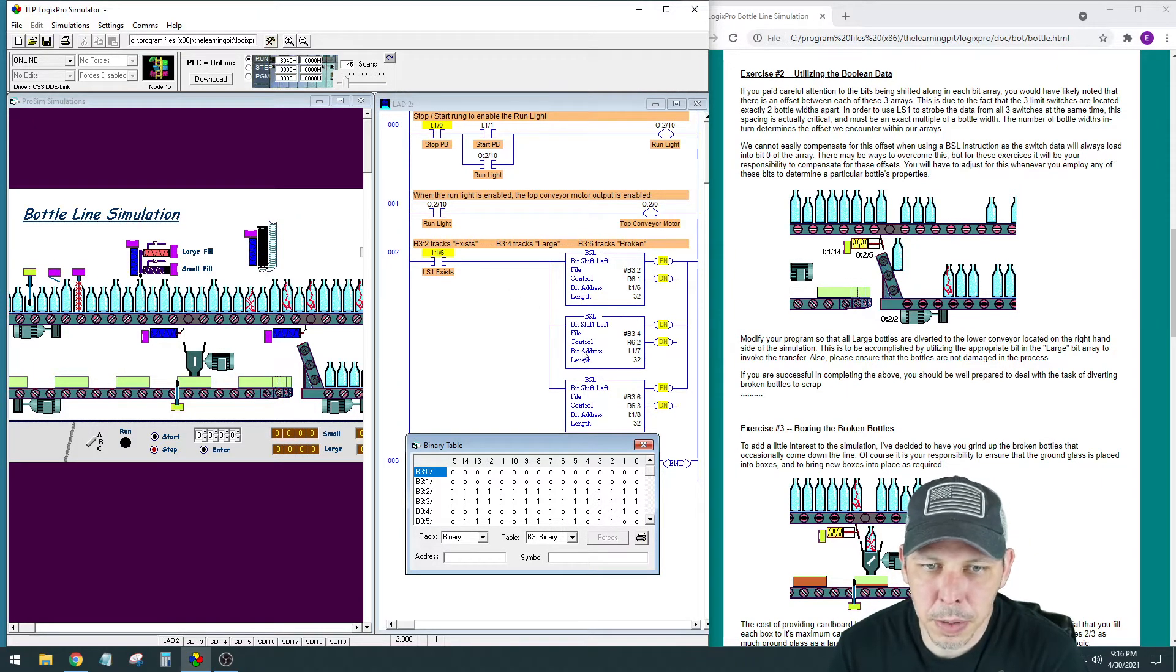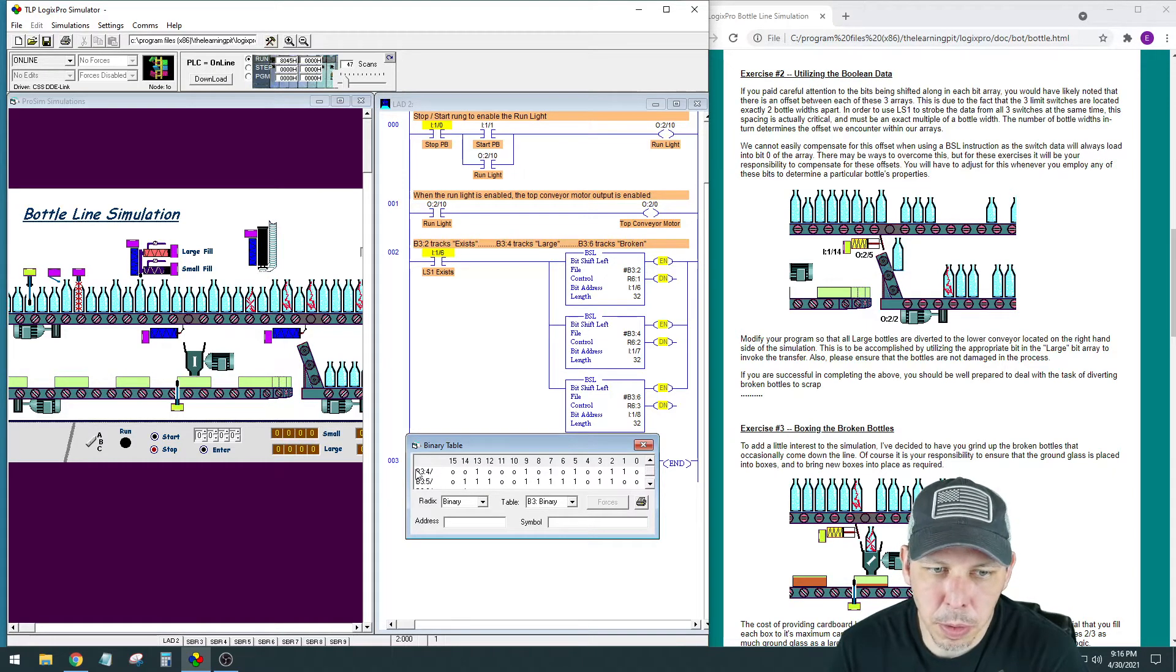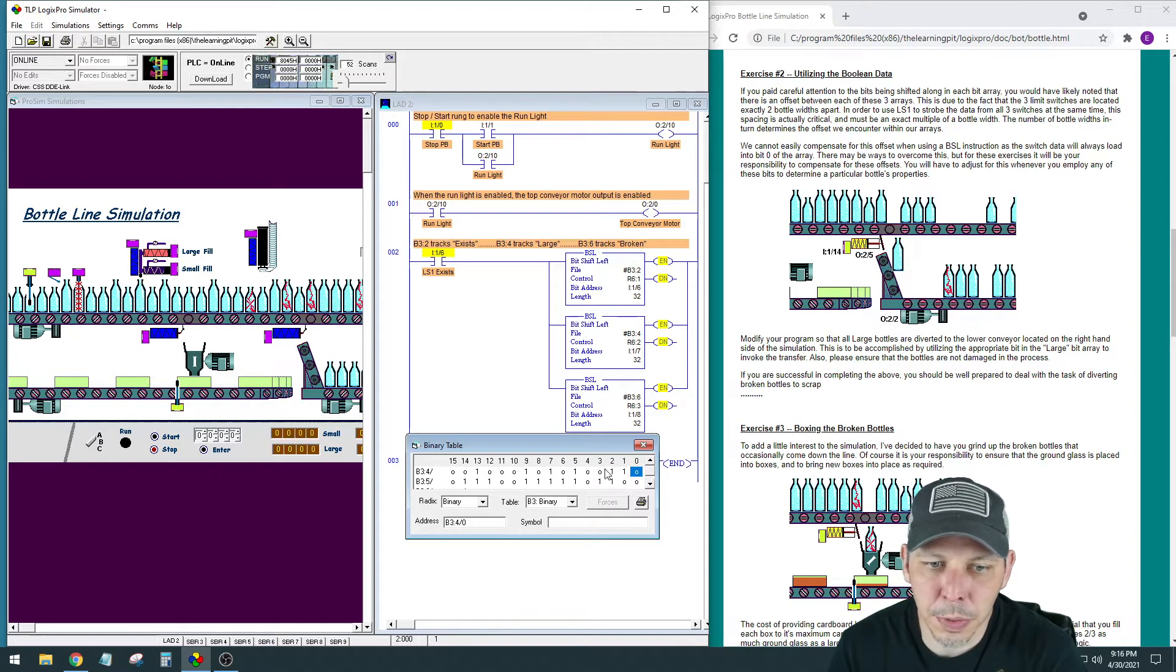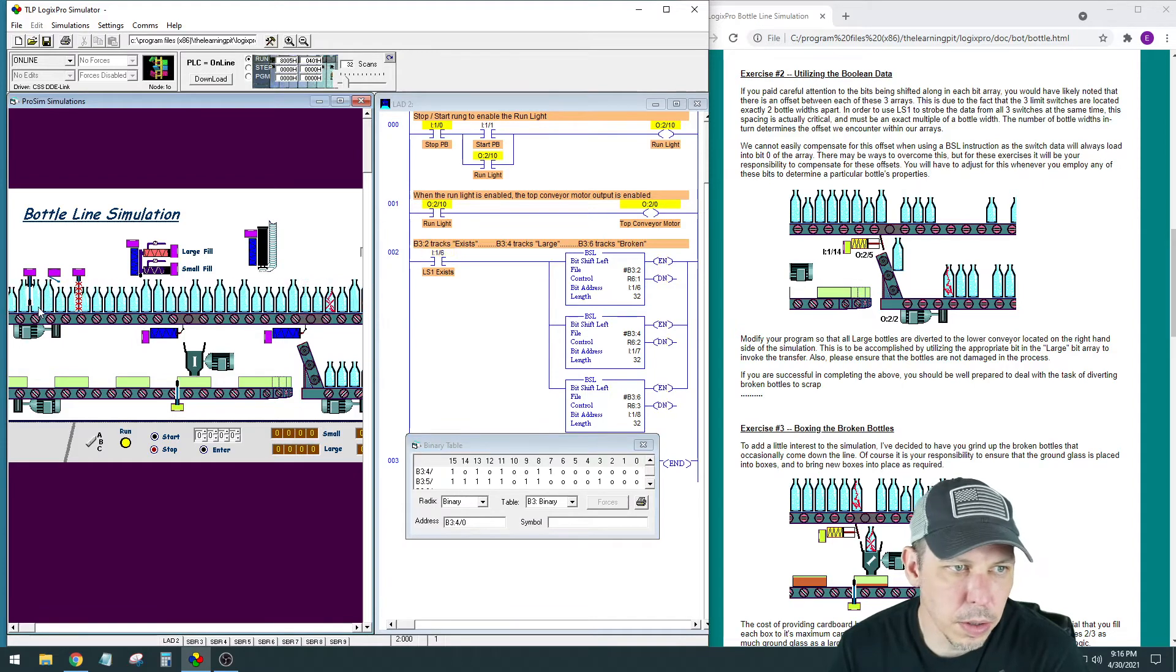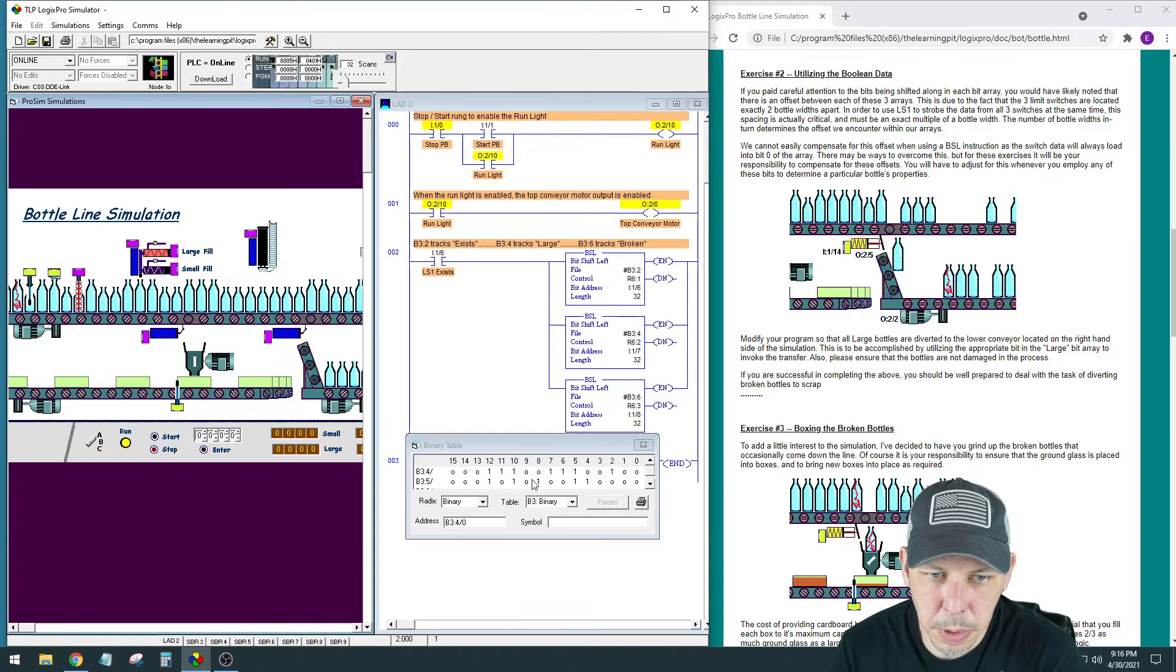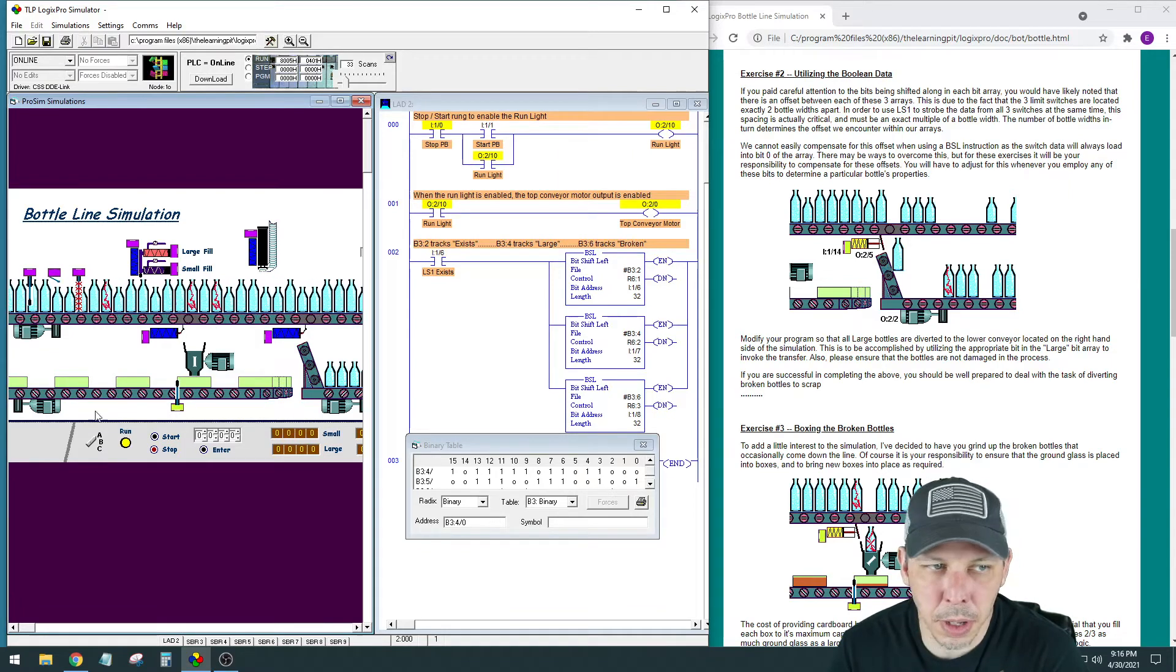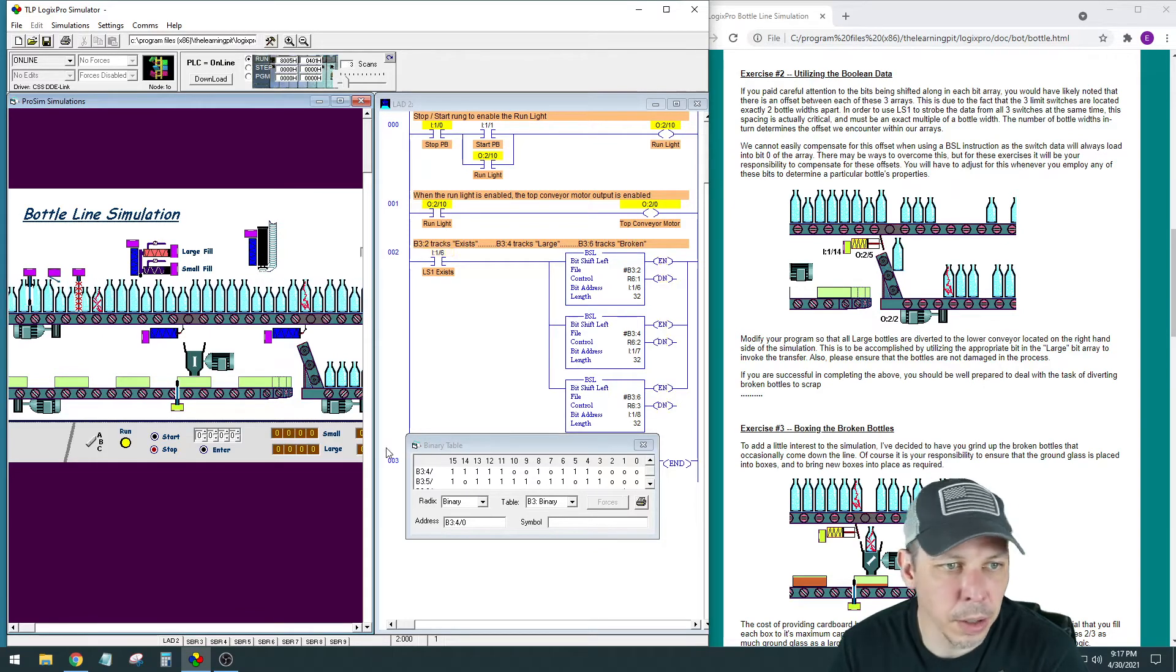Every time this bit shift is fired, it's going to B34, the word B34 bit 0 right here. Every time it records something, it's putting it in here, and then when it records the data for the next bottle, whether it's a large or not a large, it pushes the previous one over so they keep rolling over to the left. You'll see that I can run it here. There's three big ones in a row that just came in, and then two little ones and three big ones. Anytime there's a one, that means that was a large bottle that was detected. Anytime there's a zero, it means that's a zero or a small bottle in that location.